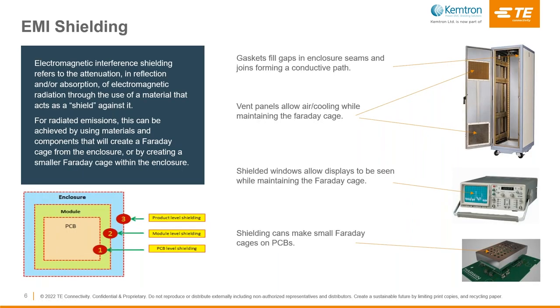For radiated emissions, EMI shielding can be achieved by using materials and components that create a Faraday cage around the electronics. This can be created at the enclosure level where the outer enclosure becomes a Faraday cage, at a module level by creating a smaller Faraday cage within the enclosure, or at the PCB level by using shielding cans to create a Faraday cage around an individual component or a group of components on the PCB.